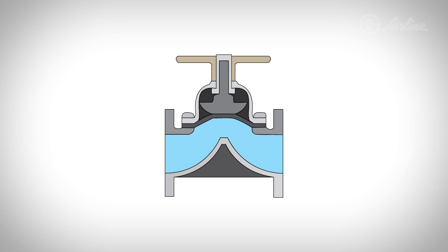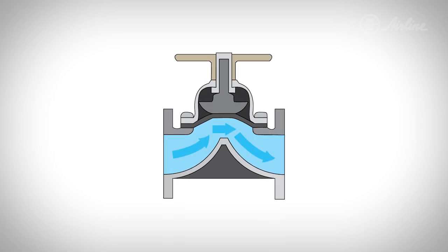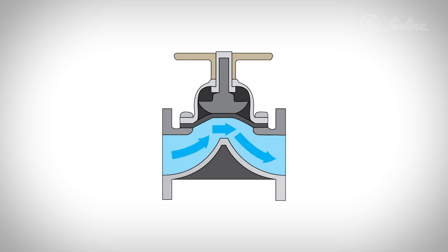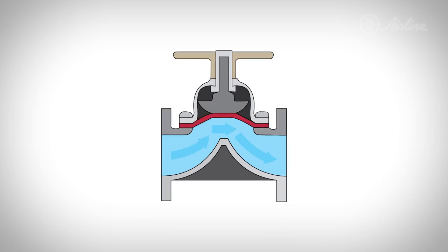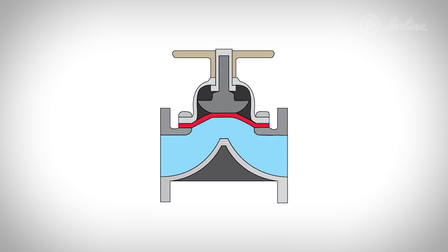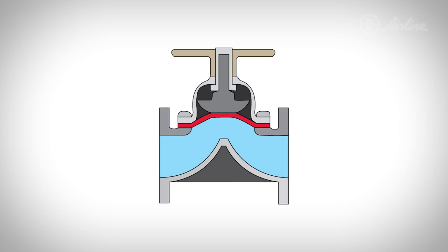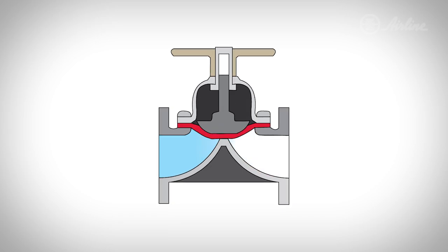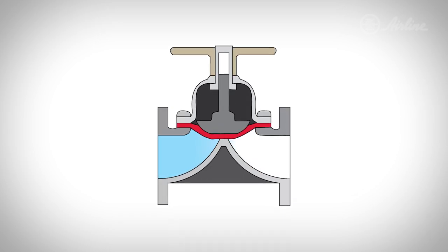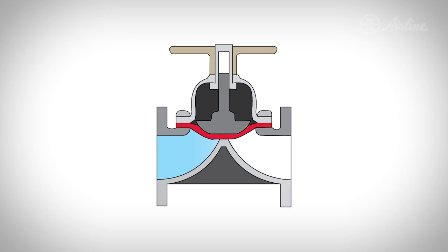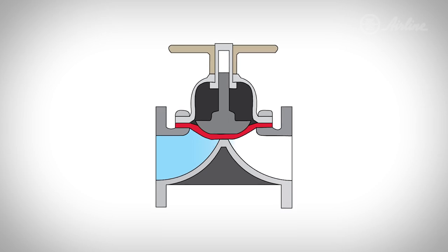Diaphragm valves, also known as membrane valves, are named after the diaphragm that extends and retracts to isolate the flow path. In this illustration you can see a non-activated diaphragm valve along with the flow path of the medium. The flexible diaphragm is located just below the compressor. When the valve is activated, the compressor pushes the diaphragm towards the valve seat. When the diaphragm completely seals the valve seat, the flow path becomes isolated.